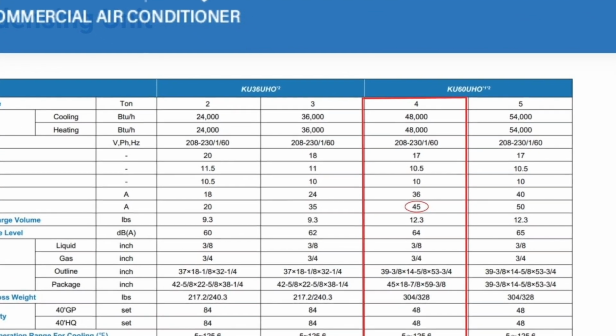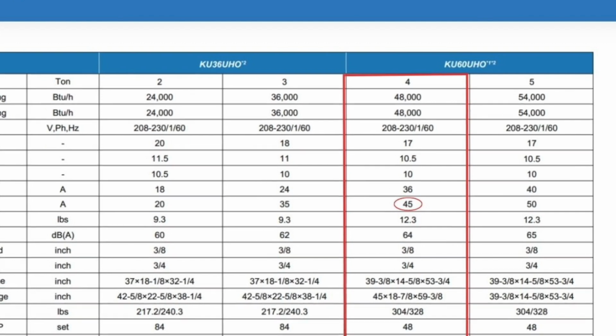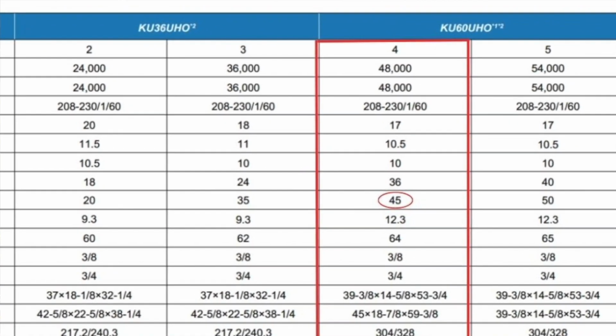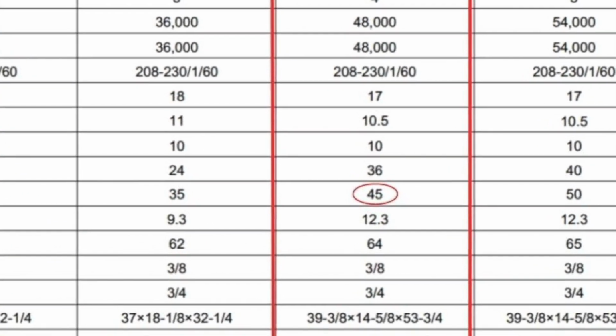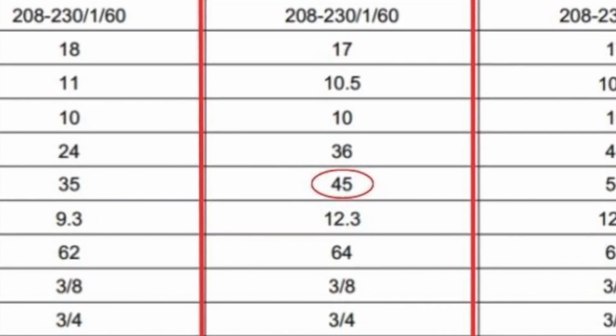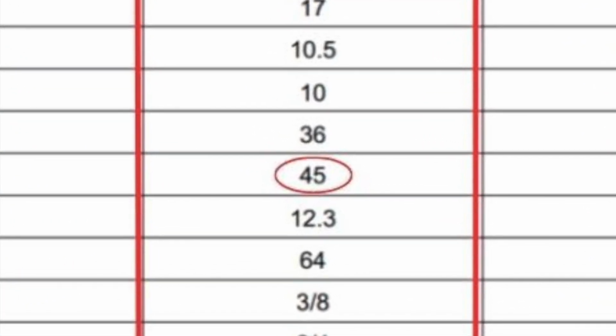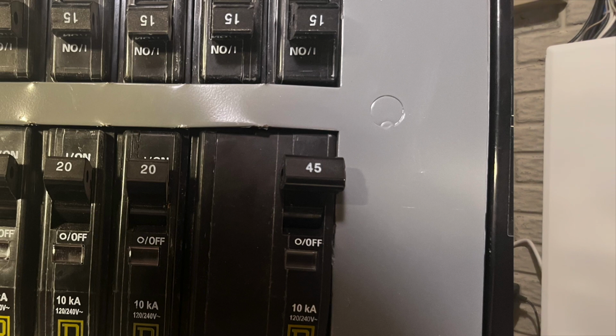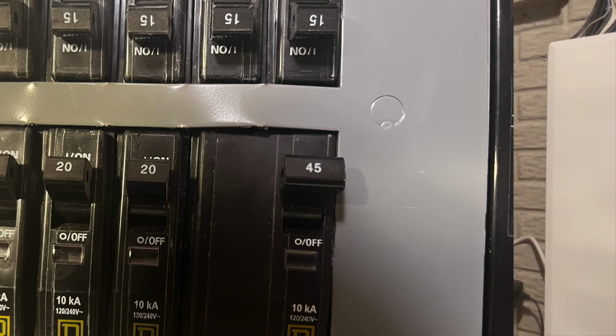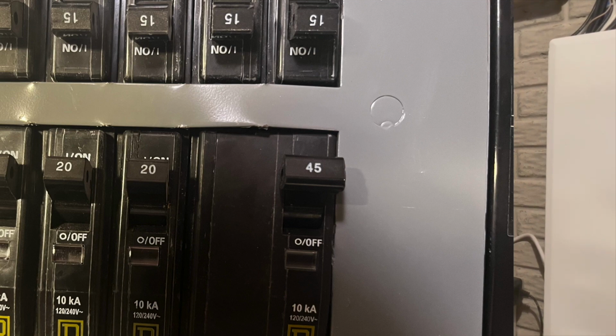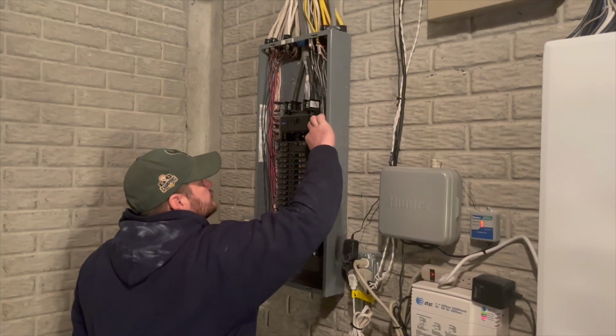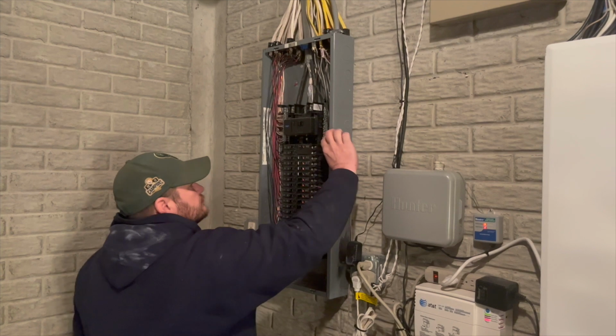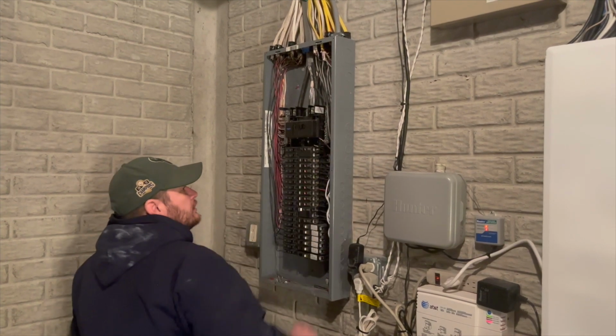circuit breaker. So the electrician has to change out, number one, the circuit breaker, but number two, the electrician also needs to make sure that the wire gauge to the heat pump is properly sized as well. In this case, we found out that the original electrician didn't pull the right gauge wire to the air conditioner, so unfortunately we shouldn't have had to replace it, but in this case we did. The electrician also installed a new disconnect switch next to the heat pump for service.